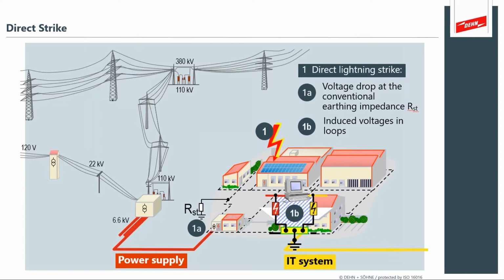So the challenges at a power generation facility are particularly complicated because they're large systems with a lot of interconnected systems. You have damage from direct strike where it can strike directly into some of the buildings in a power generation plant. But you see that you have a large collection area and you have extensive systems of power and earthing systems and communication I/O control systems. And this direct strike damage can cause a lot of ground swell. So you'll see in the earthing, this is a really good illustration showing an interconnected mesh earthing system. And so a strike on one end can actually induce ground potential rise all throughout the power system and the information technology systems at a site.